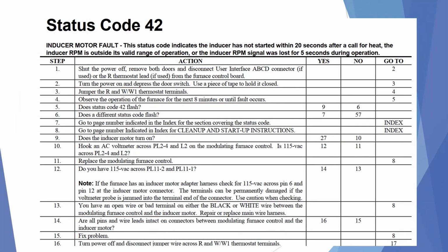On your modulating gas furnaces, you will also have an inducer motor that is an ECM motor. If the ECM motor for the inducer is faulting, you will get some type of a code, like code 42 in this particular case, that tells us that we have an inducer motor fault. Like with the other troubleshooting, they will ask you if you have 115 volts to your inducer motor. This would be the first stage of troubleshooting that would tell us that the inducer motor is powered and is ready to run when it receives signals from the control board to run.